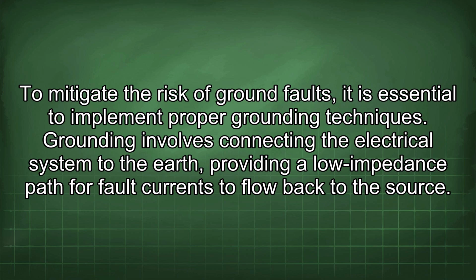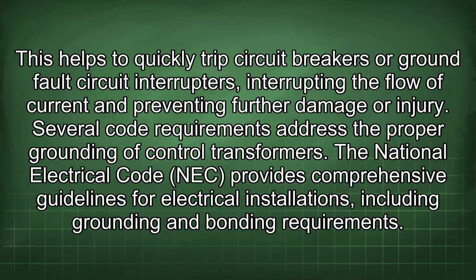Grounding involves connecting the electrical system to the earth, providing a low impedance path for fault currents to flow back to the source. This helps to quickly trip circuit breakers or ground fault circuit interrupters, interrupting the flow of current and preventing further damage or injury. Several code requirements address the proper grounding of control transformers.